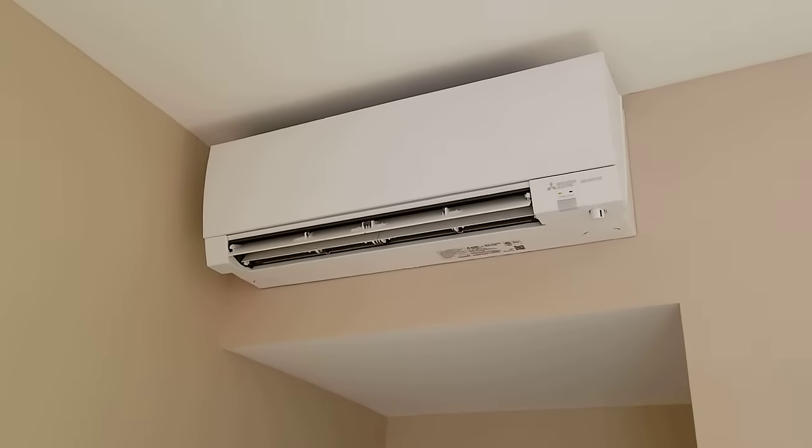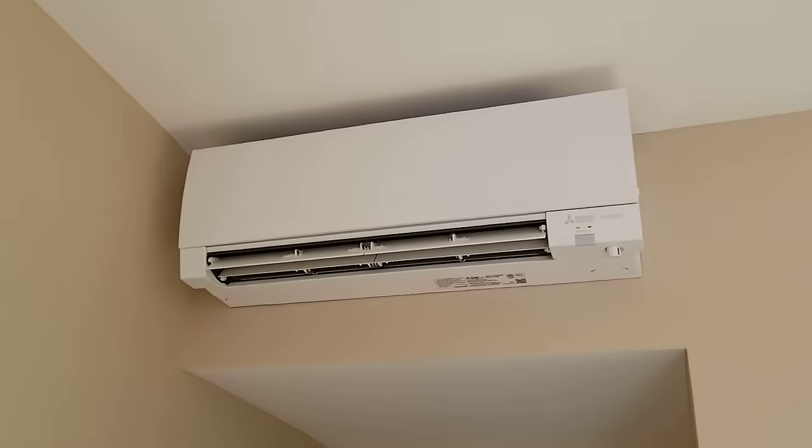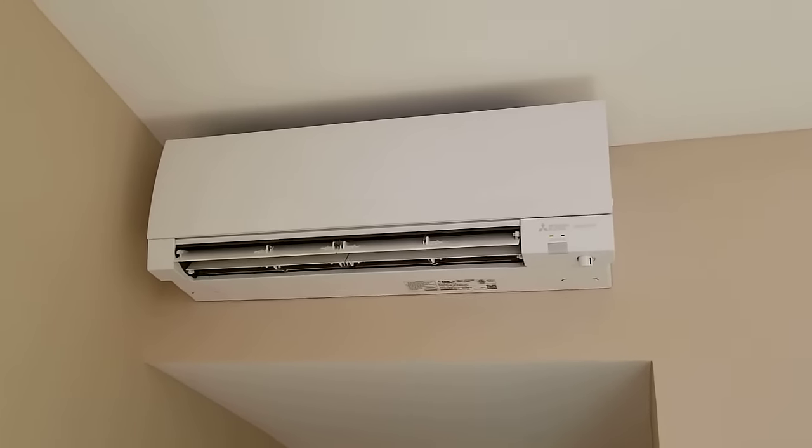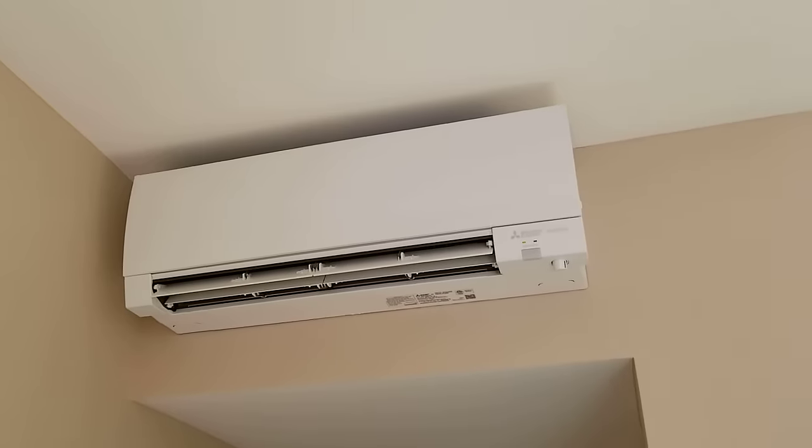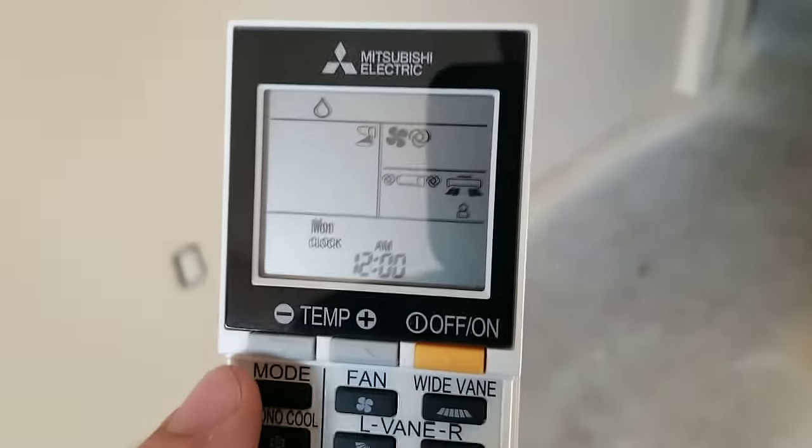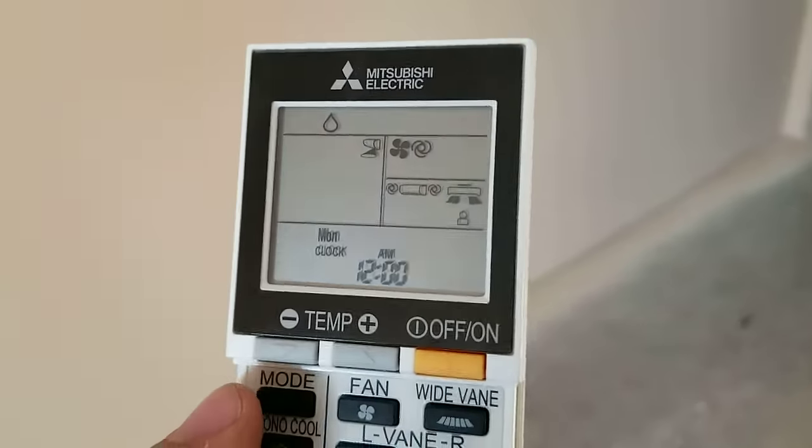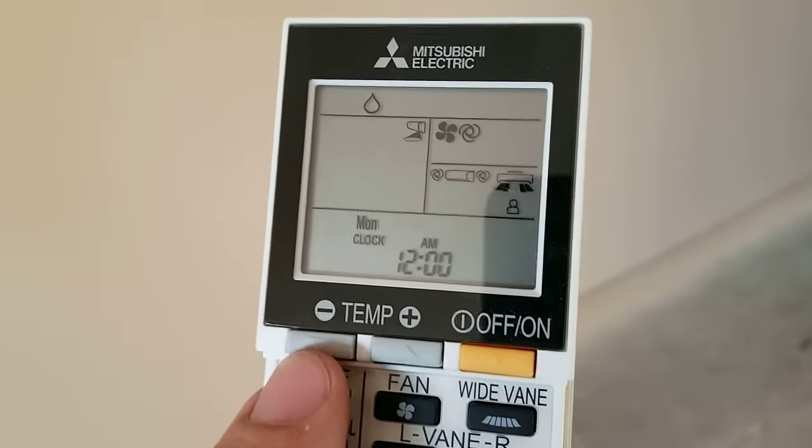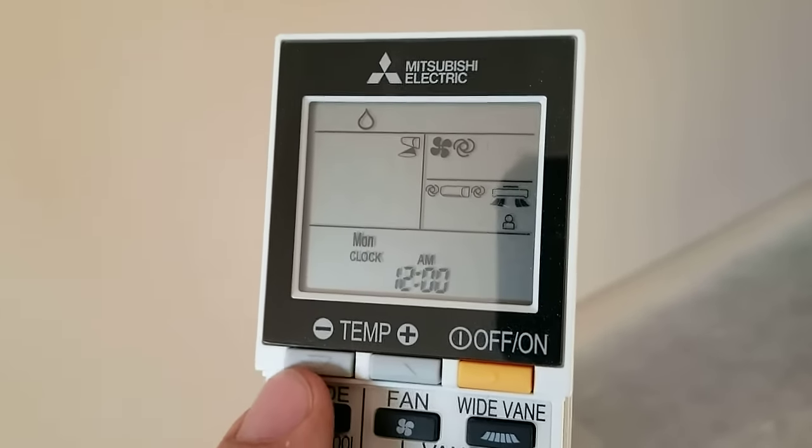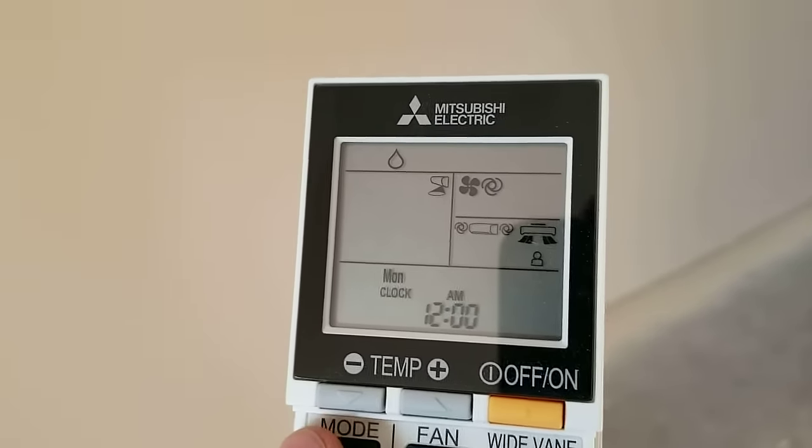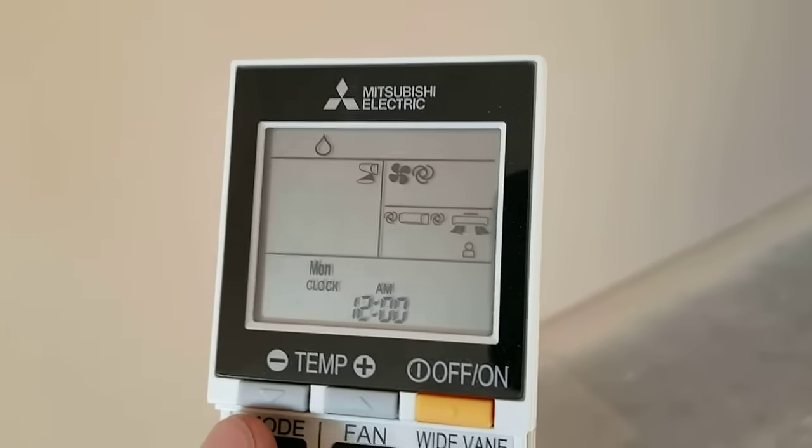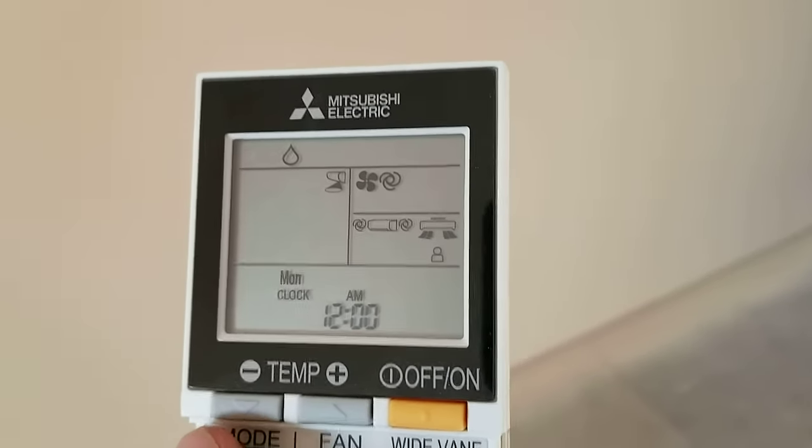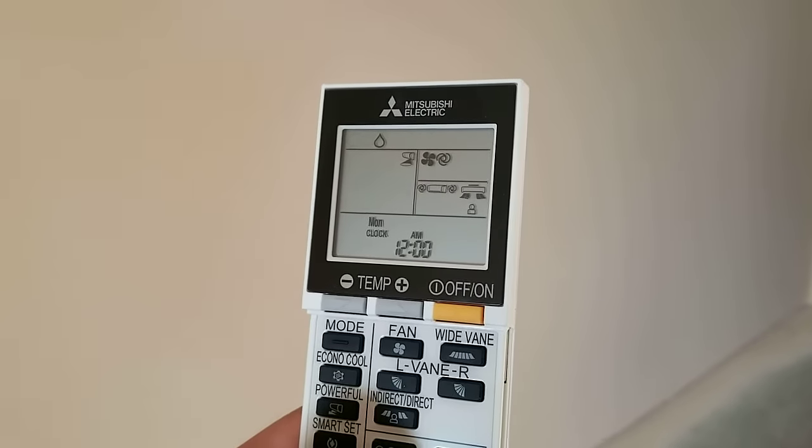The fan will blow very slowly, which allows the coil to collect a lot of moisture. The outdoor unit will run at a very high speed if necessary to get rid of that moisture. It's not going to cool your house very much, but it will cool it some in the process of removing moisture.